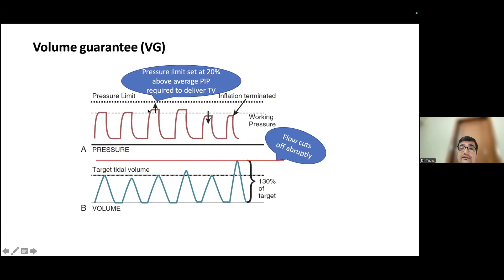So what are the pros and cons of volume guarantee ventilation? As we have seen, in volume guarantee ventilation, the tidal volume is variable throughout the ventilation. So it's actually a physiological pattern, okay? Because it has been shown that if you deliver a constant tidal volume to the lungs, that may lead to atelectasis. Whereas if you are delivering a variable tidal volume to the lung, this risk of atelectasis is less. Similarly, the working pressure is continuously adjusting, trying to catch up the target tidal volume. So this mode of ventilation is better as compared to pressure control ventilation.